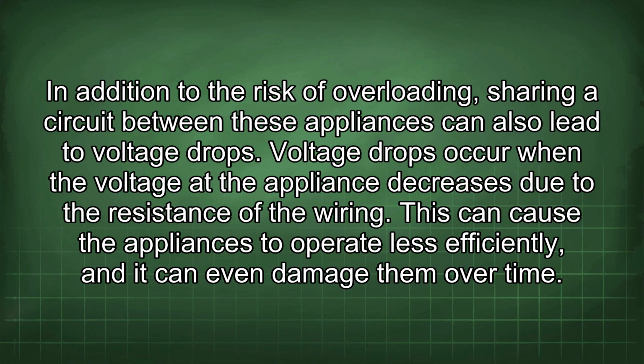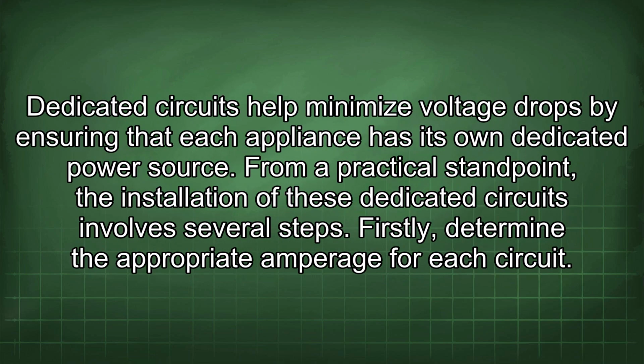In addition to the risk of overloading, sharing a circuit between these appliances can also lead to voltage drops. Voltage drops occur when the voltage at the appliance decreases due to the resistance of the wiring. This can cause the appliances to operate less efficiently, and it can even damage them over time. Dedicated circuits help minimize voltage drops by ensuring that each appliance has its own dedicated power source.